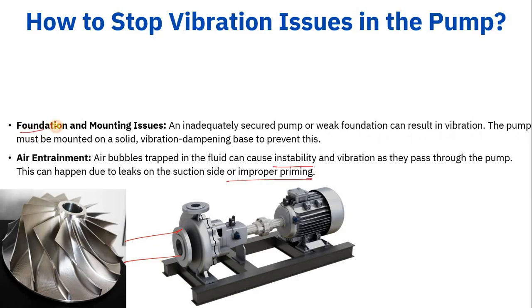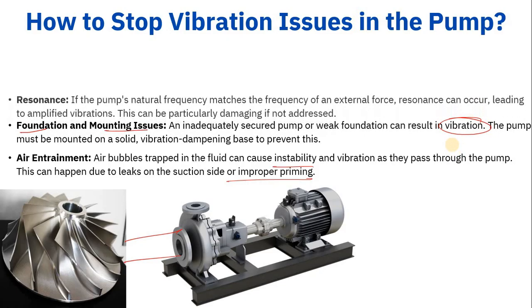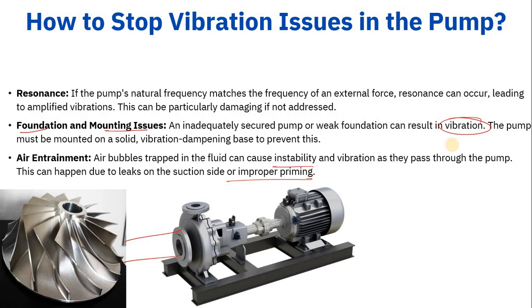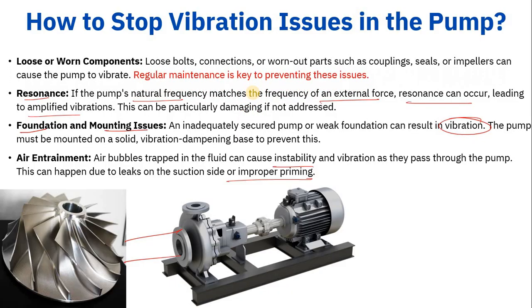Foundation and mounting issues can also cause vibration. If there is an inadequately secured pump or a weak foundation, it will create vibration. This also happens when the foundation is not designed to support the weight of the pump. Additionally, resonance is a concern: if the pump's natural frequency matches the frequency of an external force, resonance occurs and leads to amplified vibration, which can be particularly damaging. Mechanical and vibration personnel must always check the vibration levels of rotating equipment during rounds.